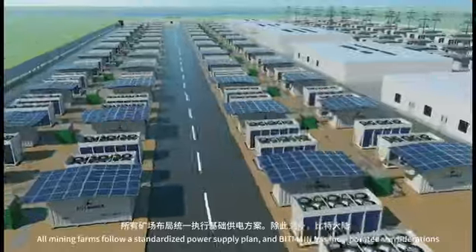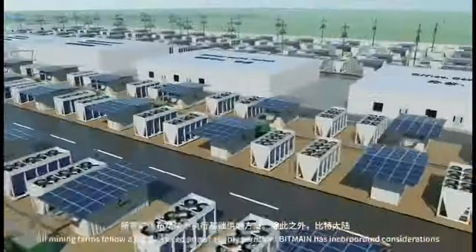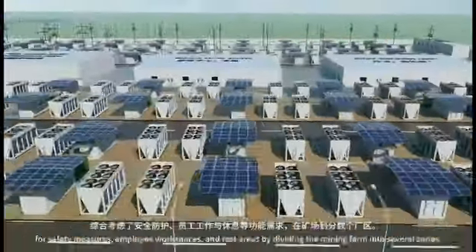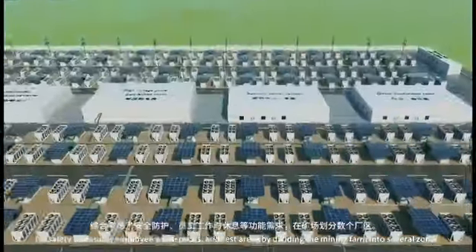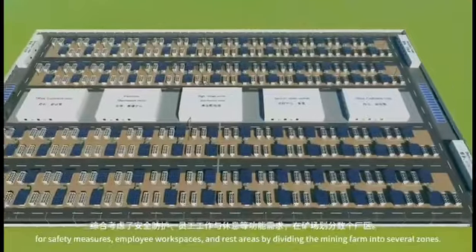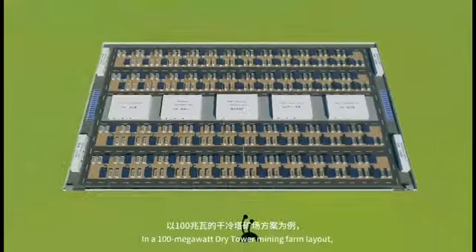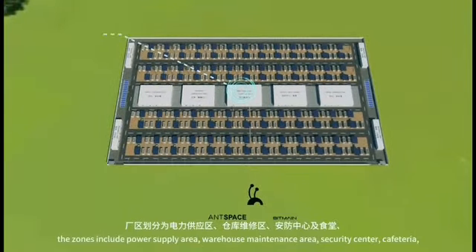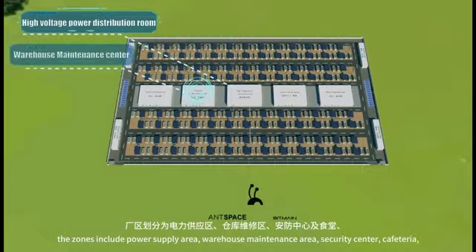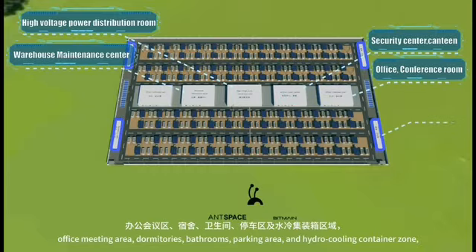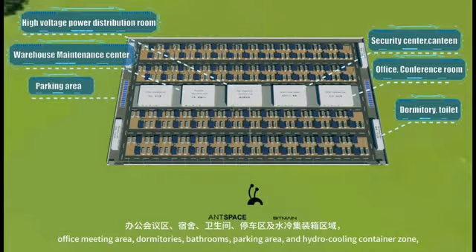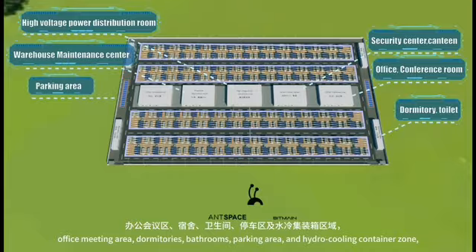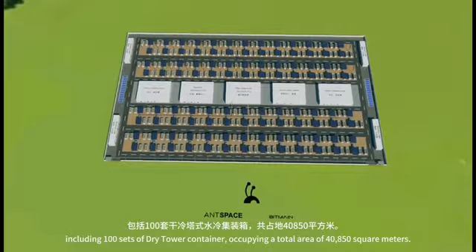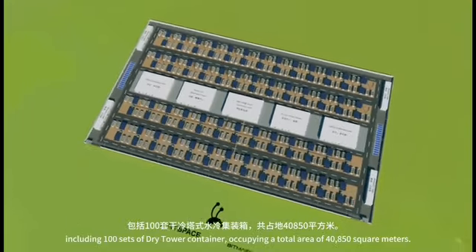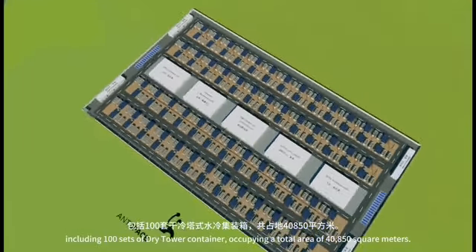All mining farms follow a standardized power supply plan, and Bitmain has incorporated considerations for safety measures, employee workspaces, and rest areas by dividing the mining farm into several zones. In a 100-megawatt dry tower mining farm layout, the zones include power supply area, warehouse maintenance area, security center, cafeteria, office meeting area, dormitories, bathrooms, parking area, and hydro-cooling container zone, including 100 sets of dry tower container, occupying a total area of 40,850 square meters.